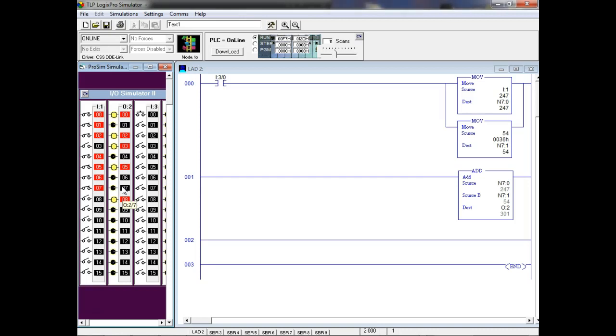So we got two instructions. We got the TOD and FRD that can take something that gives me a BCD input. So I can input the number 153, and then it'll convert it from decimal BCD over to what? Binary. We can do math with it, right? And then when I want to display it, I can send it back out, I can convert binary to BCD. So we got two instructions. Every PLC that I've ever worked with has that ability. Because why? We need to be able to input numbers, and we need to be able to see numbers.